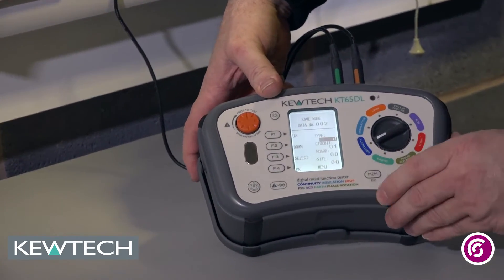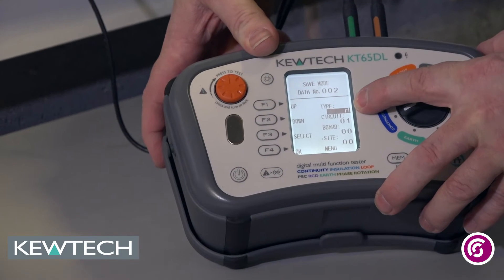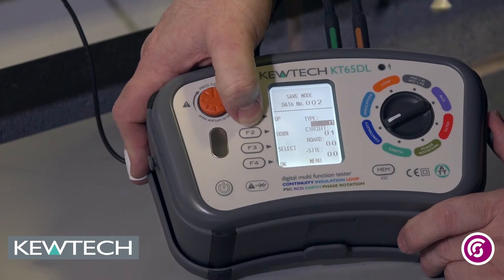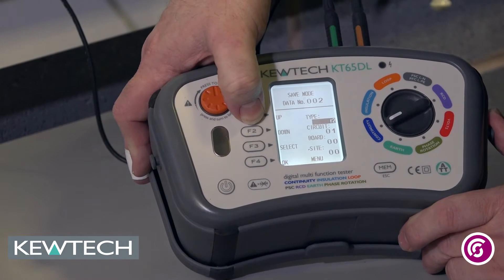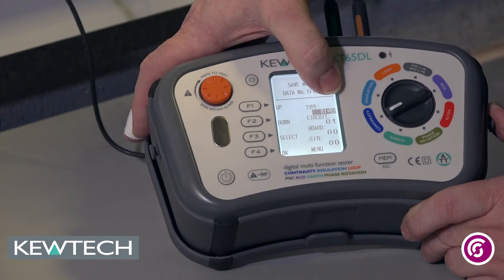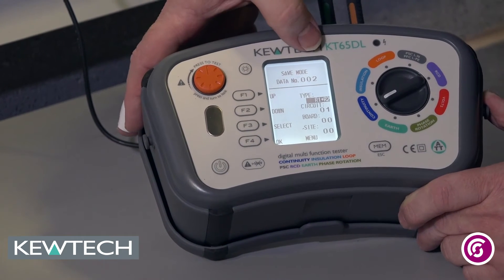By pressing MEM for memory, as you can see there it says R1. I was actually doing an R1, R2, so I press the F1 button — R2, Rn, R1 plus R2 — which is what I want. So that's the R1 plus R2 value.